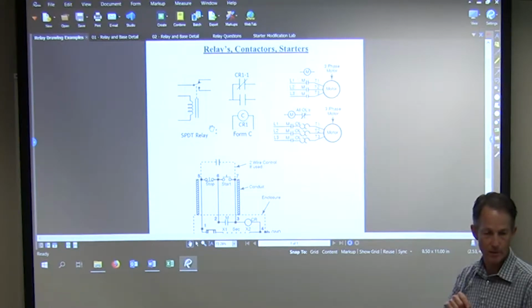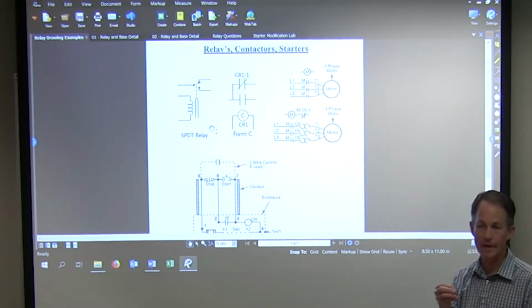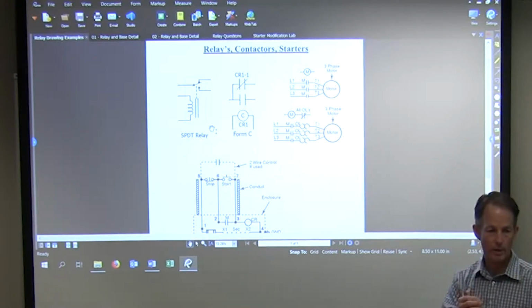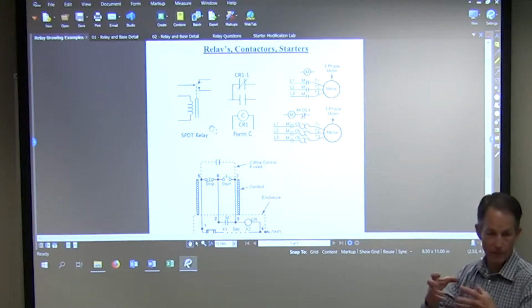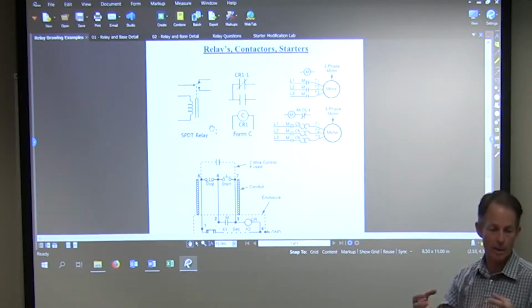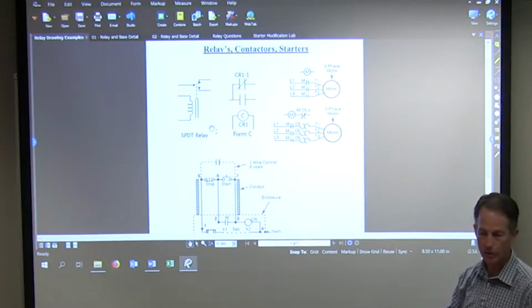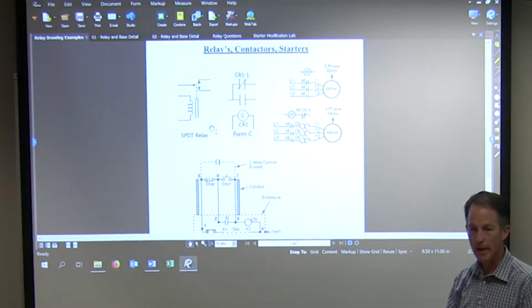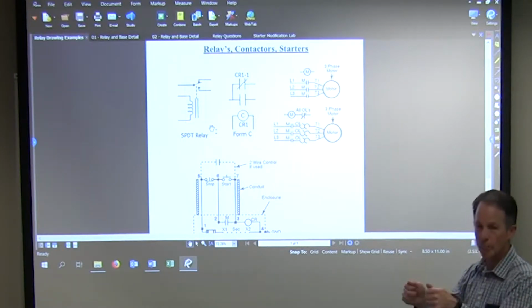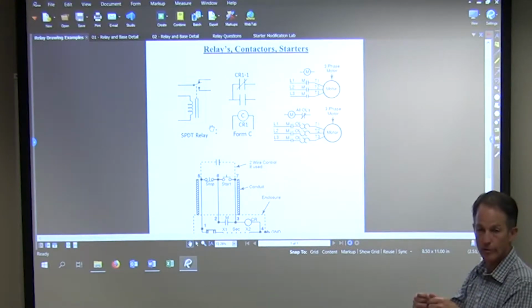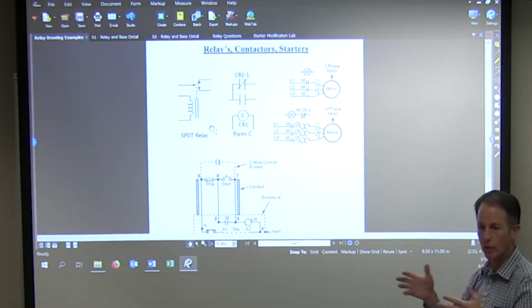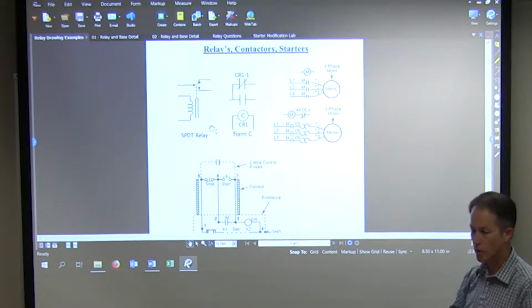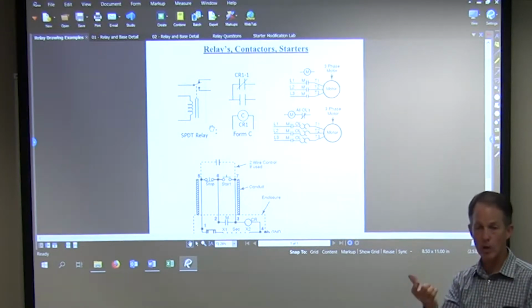Not enough to pull it in. Yeah, it won't pull the contacts in. It can't generate enough of that electromagnetic field to make the electromagnetic part work. So it doesn't work. But yeah, when you put your meter across it, you'll see 24 volts if it's a 24 volt circuit, 120 if it's 120. And you should see it because it is a load. There is a drop in voltage there.